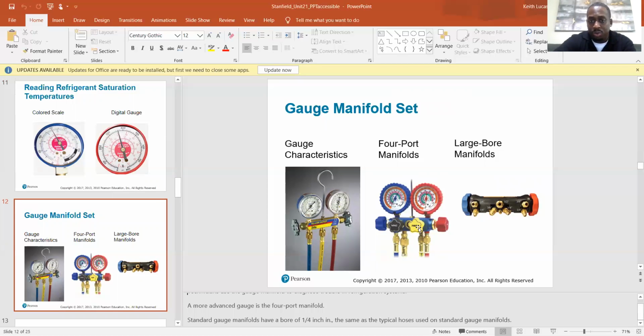Not that you can't do a vacuum with the yellow hose, which is what you would do if you had a regular 3-port setup. But if you got the 4-port, might as well use the bigger one so you can try to get that evacuation done a little quicker, even though they're pretty unpredictable. So standard gauge manifolds have a bore of 1/4 inch, the same as the typical hoses on a standard gauge manifold set.